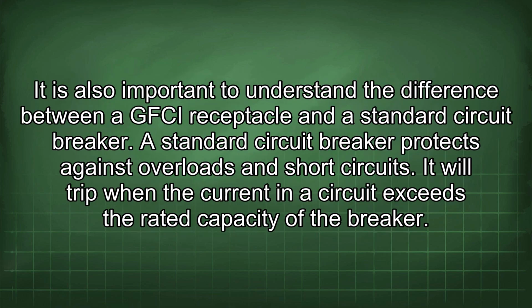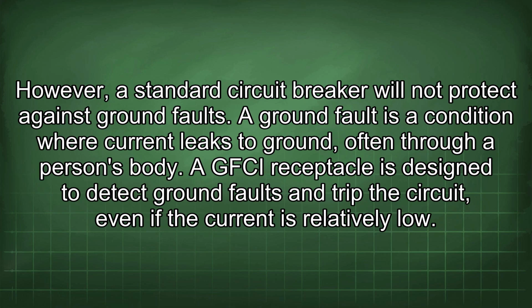It is also important to understand the difference between a GFCI receptacle and a standard circuit breaker. A standard circuit breaker protects against overloads and short circuits. It will trip when the current in a circuit exceeds the rated capacity of the breaker. However, a standard circuit breaker will not protect against ground faults. A ground fault is a condition where current leaks to ground, often through a person's body. A GFCI receptacle is designed to detect ground faults and trip the circuit, even if the current is relatively low.